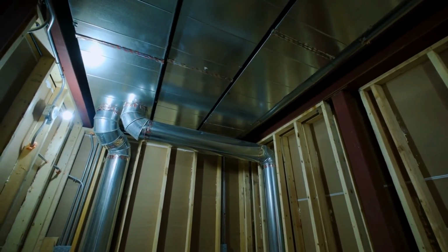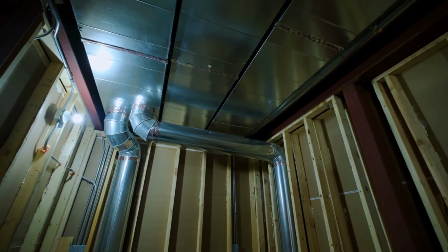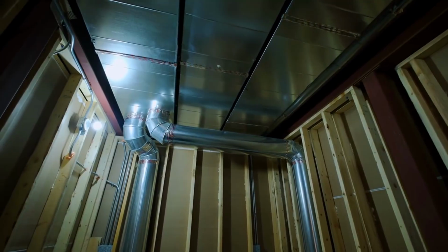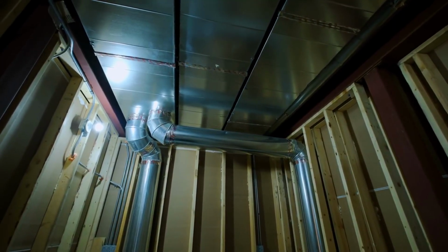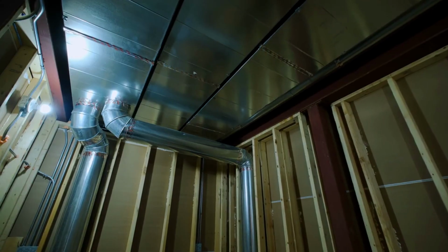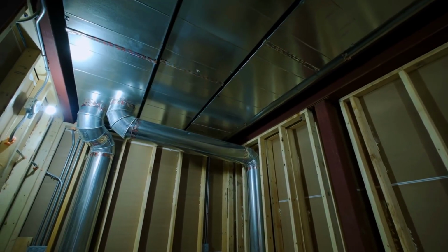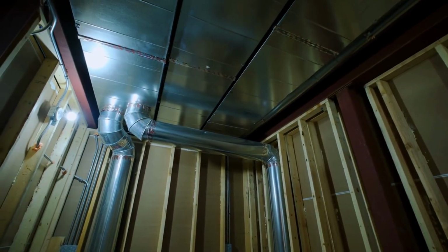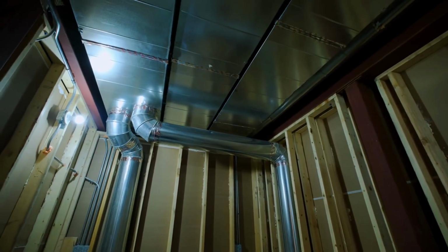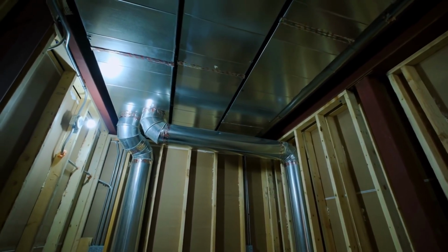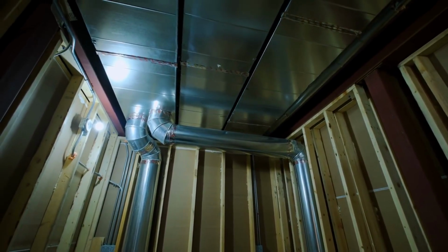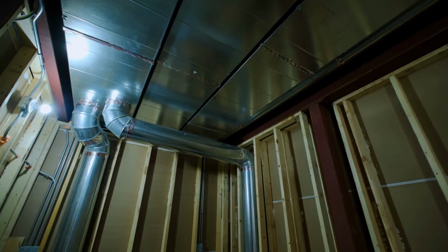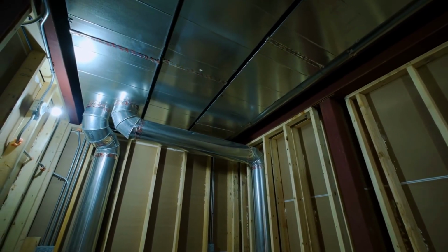For core corridors without significant loads, constant air volume boxes can be used, with the flow set to the greater of 0.06 CFM/SF or the air transfer requirements. B. For terminal heating, options such as electric baseboard or hot water fin tube radiation may be needed in certain locations, like top floor or slab on grade corridors, or those over unheated basements. Other options for heating include fully recessed wall-mounted convectors or recessed cabinet unit heaters.